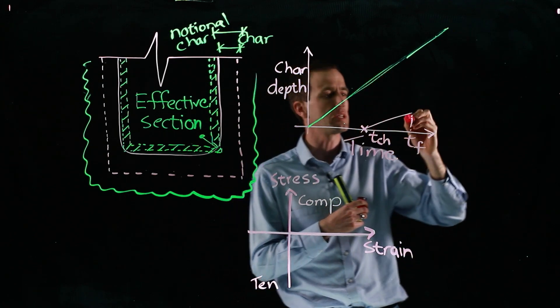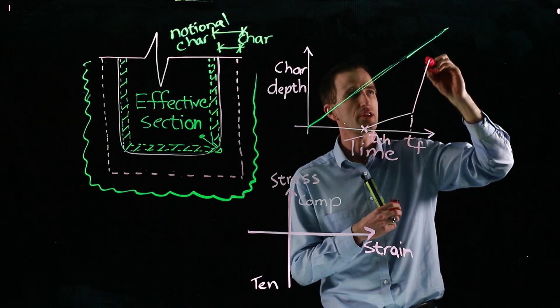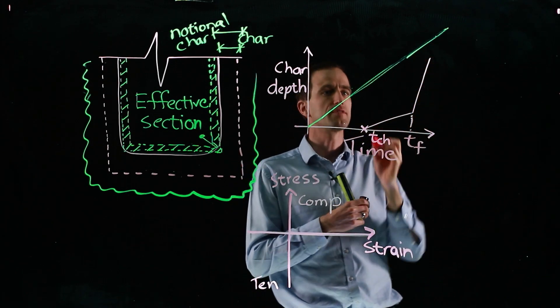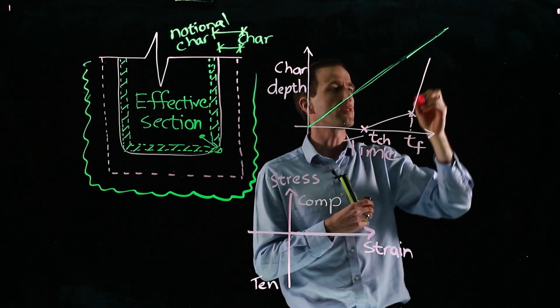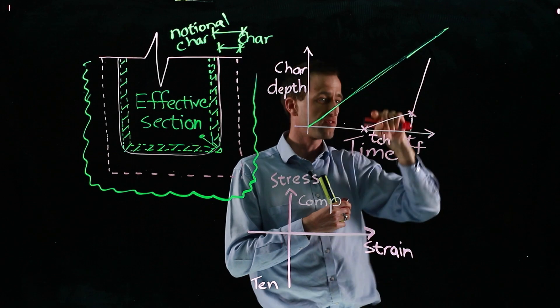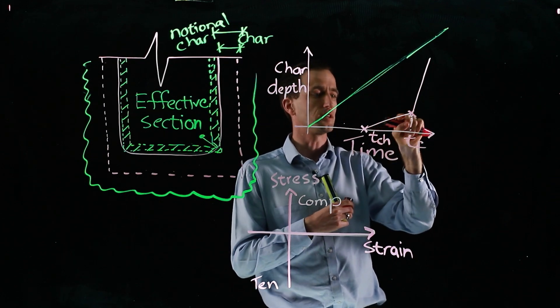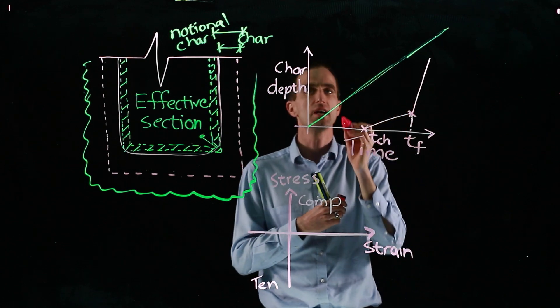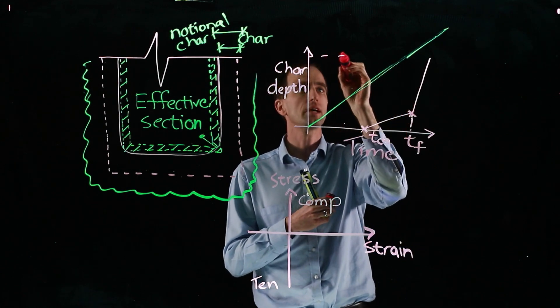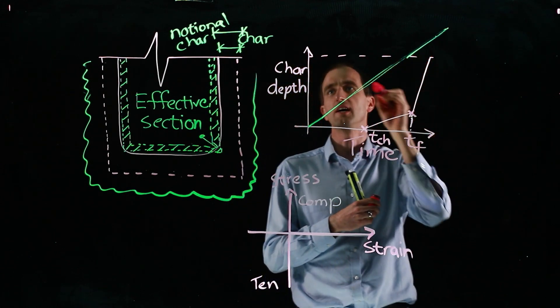Actually in excess of the normal charring rate. So from here, it'll then rapidly increase at about four times the rate of the original and about double this rate because of the preheating effect. And that occurs until we have a charring depth of about 25 millimeters.